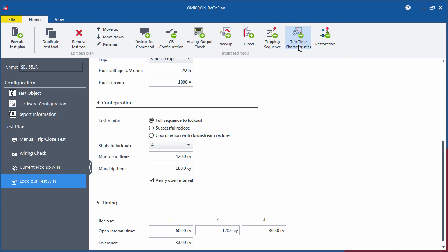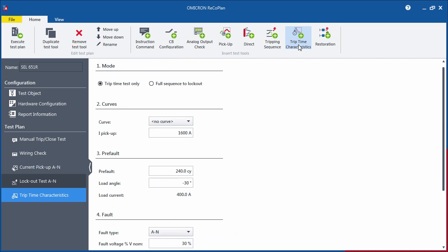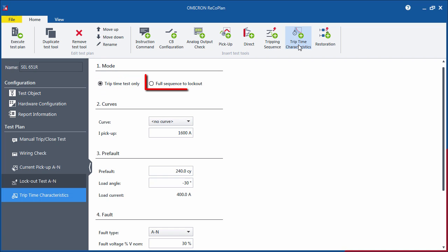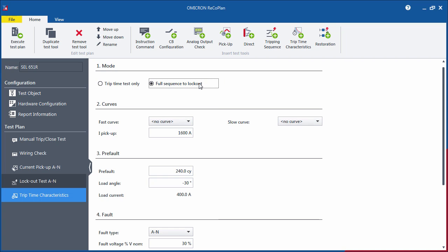The Trip Time Characteristics tool tests the tripping characteristic of a recloser control. There are two test modes available. The first mode is used for testing a single curve and the second mode for testing up to two curves commonly used in a fuse saving scheme. For this tutorial, we will focus on the test of both the fast and slow curves in the full sequence to lockout mode.